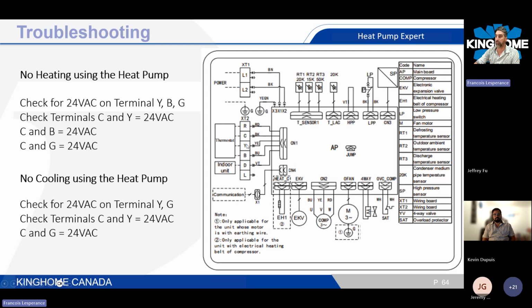But if you don't have power between C and Y, so you always have to put your probe on your common port and then follow your 24-volt lead. So if you do not have power between C and Y, C and B, this is meant to be a connection issue, or it's coming from the thermostat. It's not from the heat pump.